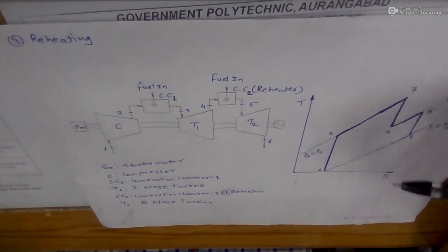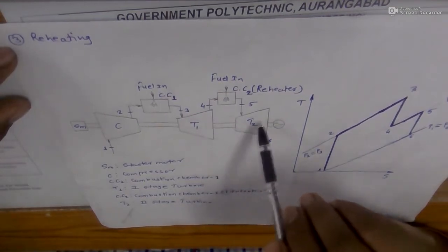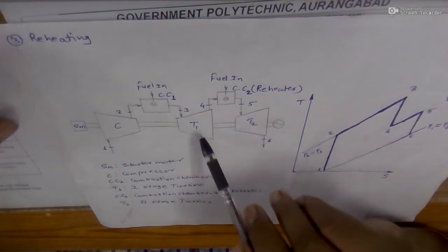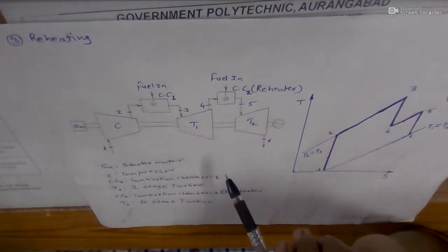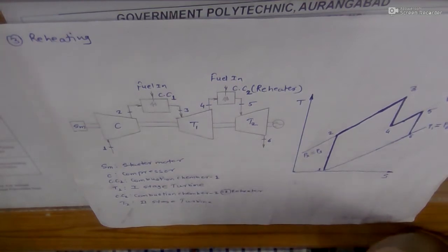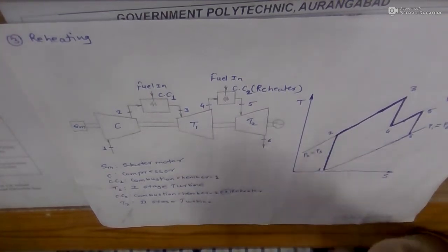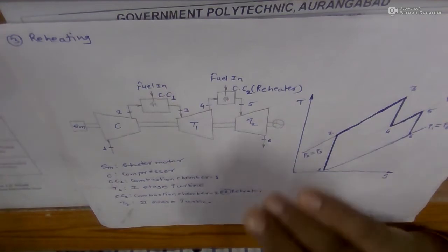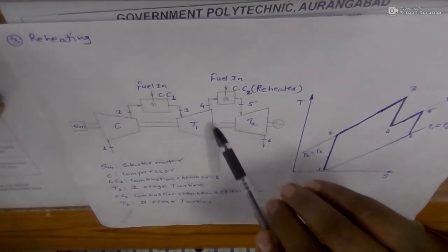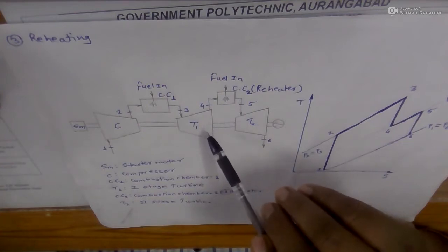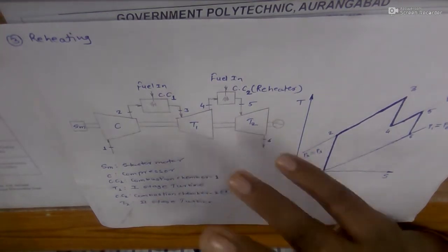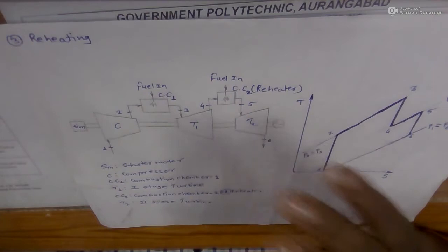In this method, if you notice properly, instead of a single turbine we have two turbines. As in the case of regeneration, where we use waste gases from turbine 1 to heat up the output air from the compressor, in this reheating process we utilize the exhaust of turbine 1 to expand further in another turbine, in order to utilize its contained energy to convert it into electric energy.